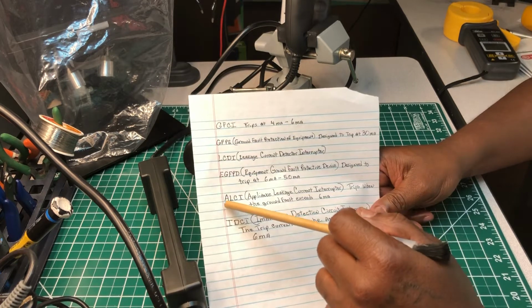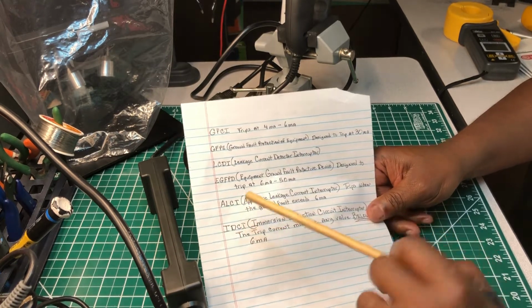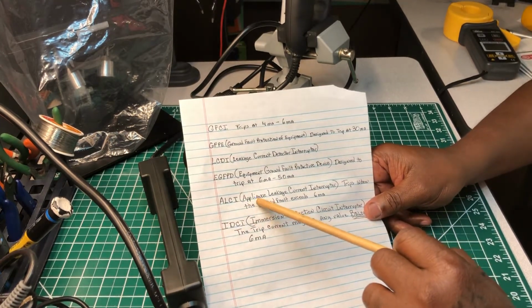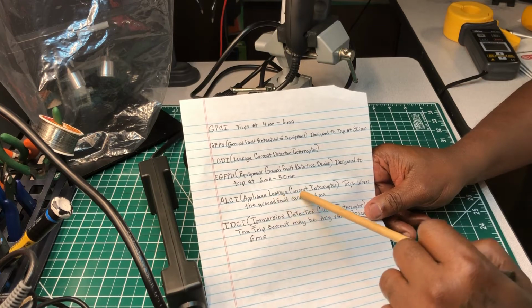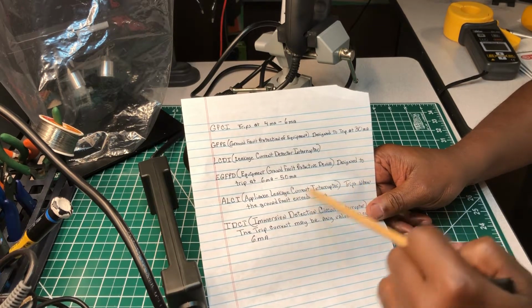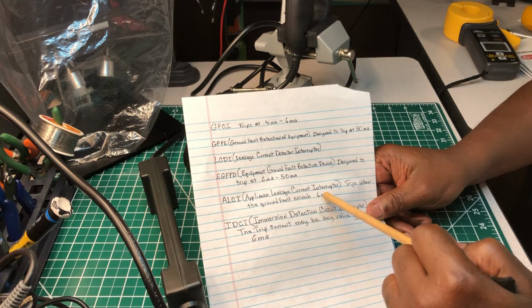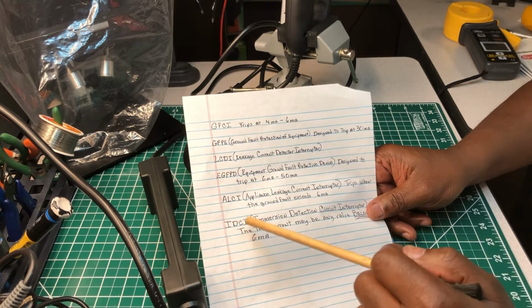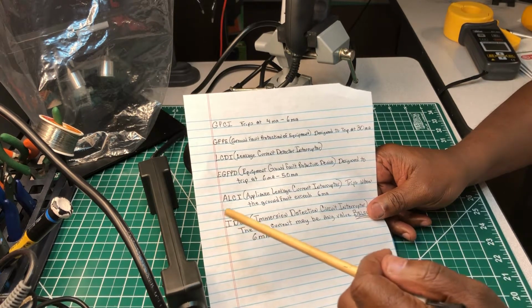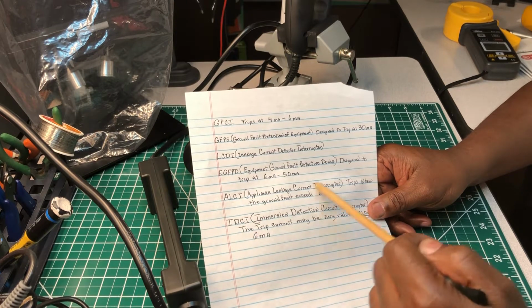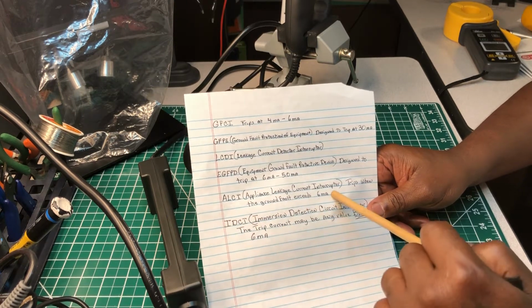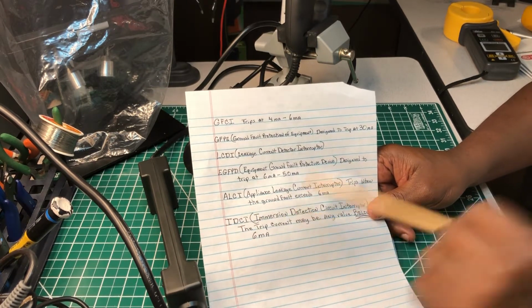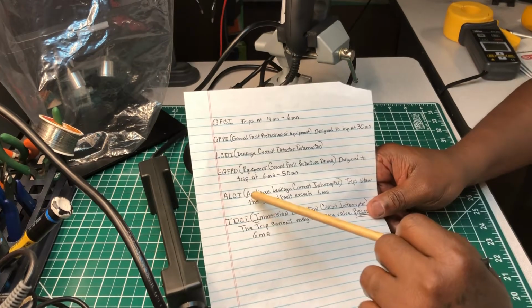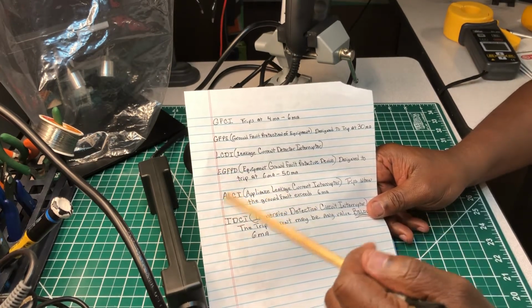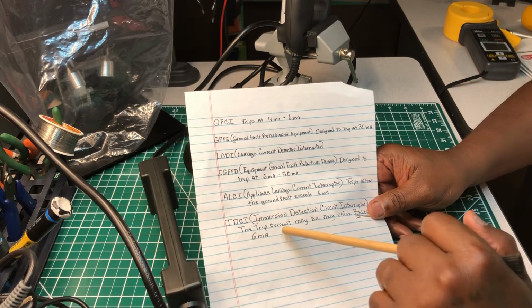There's another one. It's ALCI, and that stands for Appliance Leakage Current Interrupter, and that trips when the ground fault exceeds 6 milliamps. So that simply means from 0 to 5 milliamps, 5 is close to 6, but you're okay. Anything over 6, you're going to cause it to trip. That's when you have to go and probably hit that reset button in whatever appliance you're using. But that's what that is, a circuit interrupter.